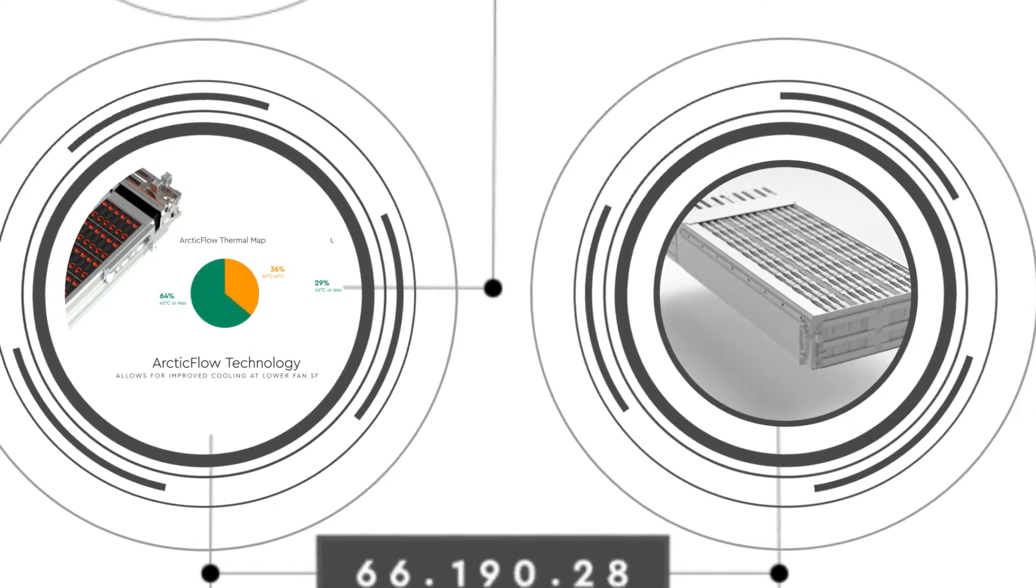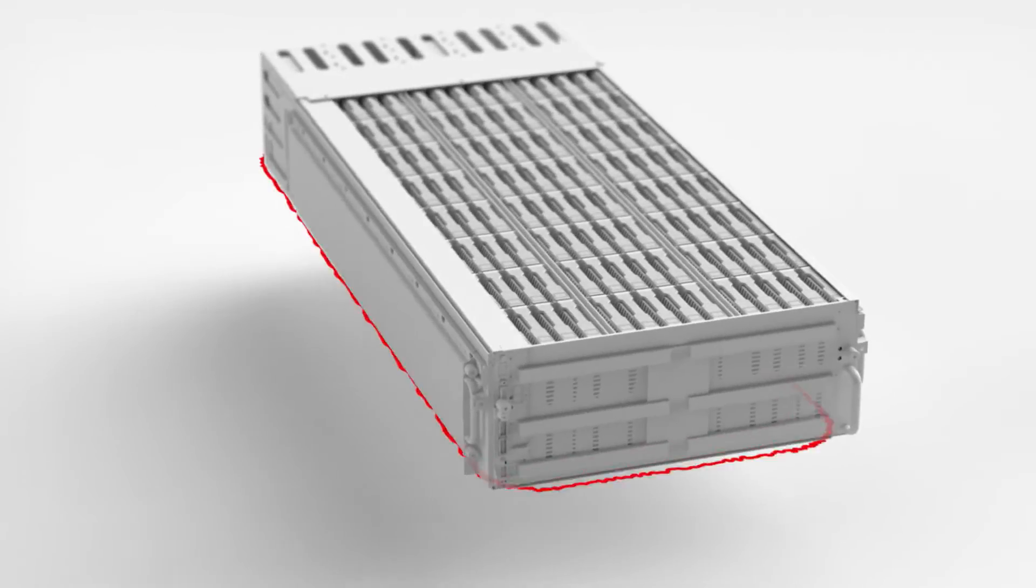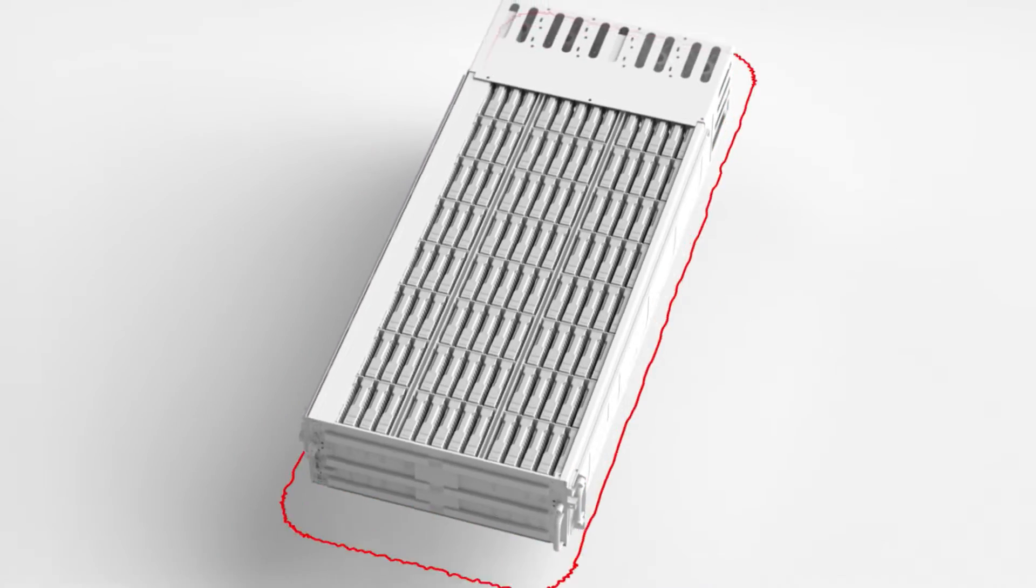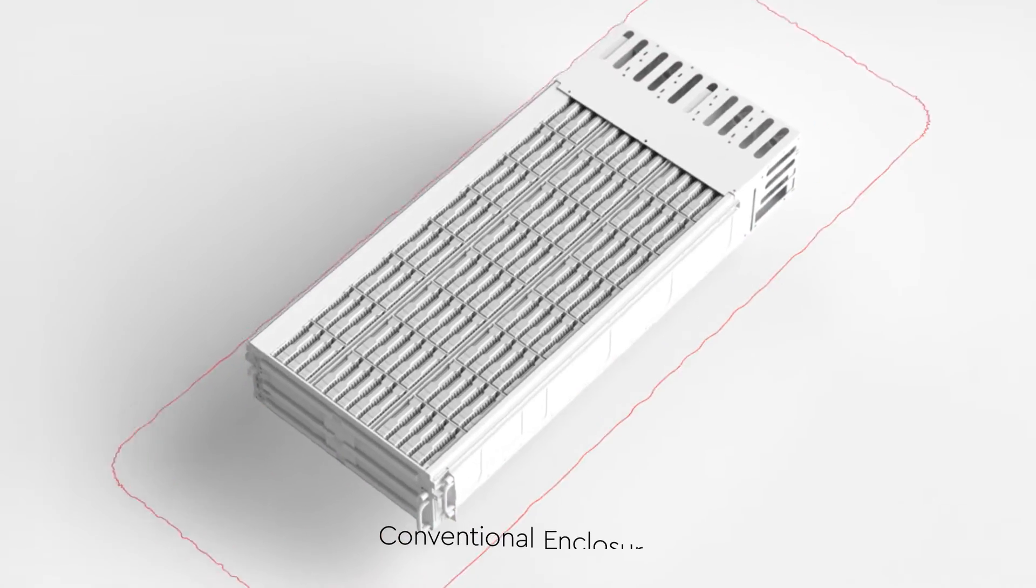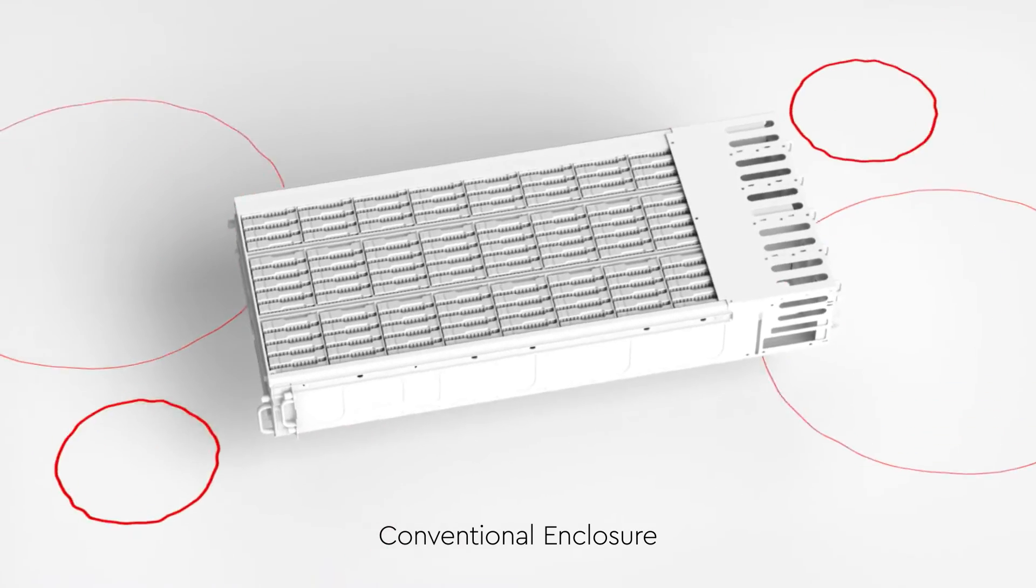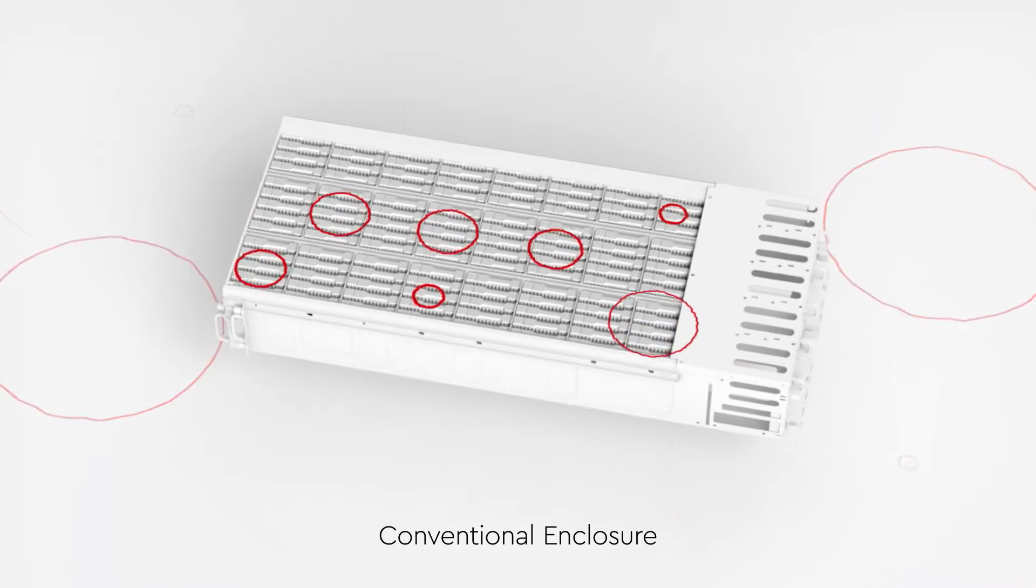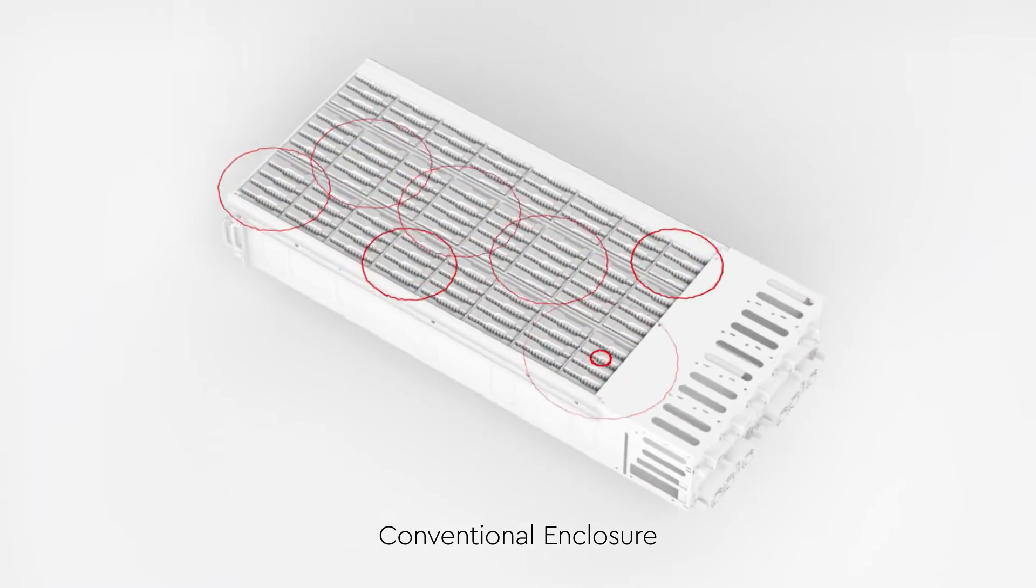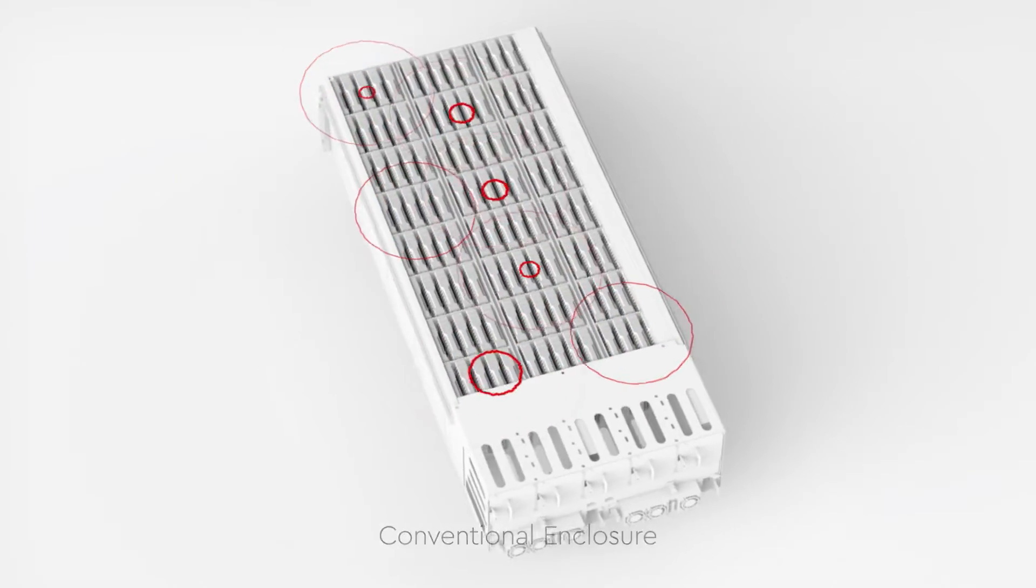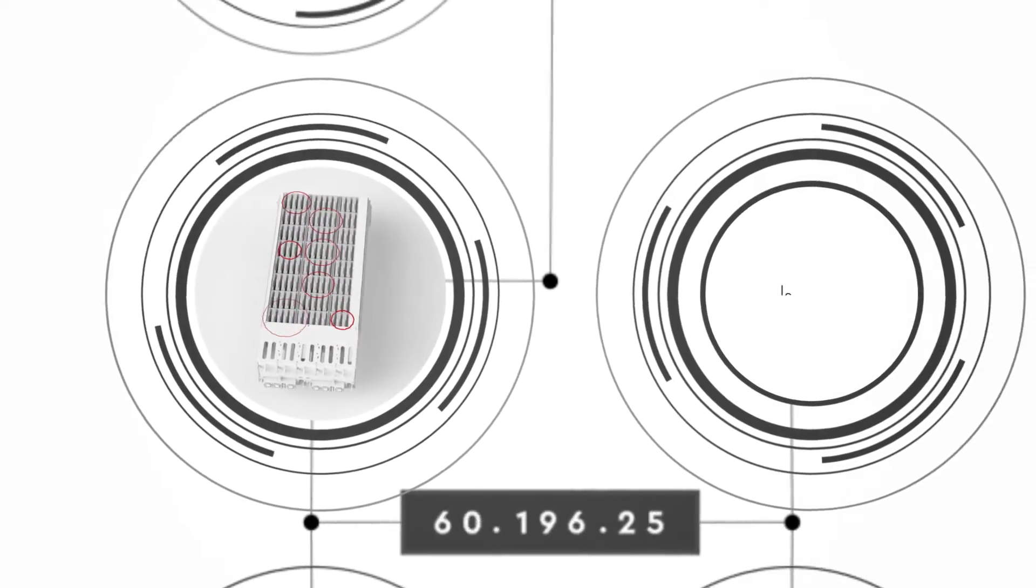Vibration is another enemy of hard drive efficiency, affecting the positioning of the read-write heads, which can cause errors and lost performance. External vibration can come from fans, servicing, even sound waves. Plus, each drive in an array creates its own vibrations that can affect the drives around it.